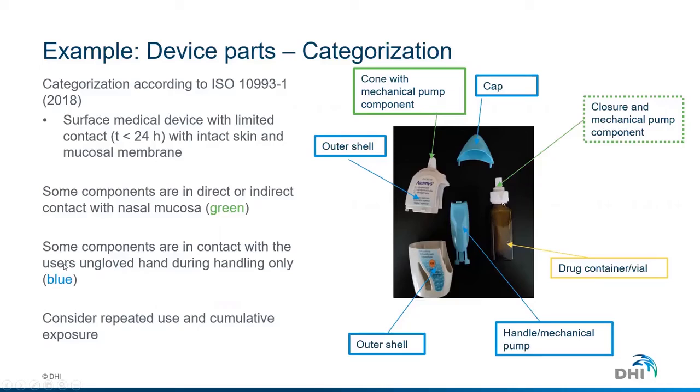Then there are some components that are only in contact with the hand during handling of the device. That's the outer shell and the mechanical handle and pump and the cap. They are only handled by hand and may be evaluated as quite non-invasive and pose a very low biological risk. And then you need to consider how will your users use this device. That will be used maybe daily, and the users will use it either for a short period of time during active treatment, or for a longer period of time, because this is a medicinal product that is used to treat allergies, for instance.